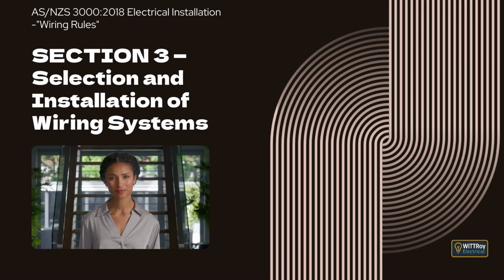The copper sheath must have enough cross-sectional area and conductivity so it can safely carry both neutral current and earth fault current. The ESR system is only permitted in installations that use the MEN earthing system, and it must start at the point where the neutral and earthing conductors are connected together to form the MEN connection. If at any point the combined protective earthing and neutral conductor is changed so that the neutral and the protective earth become separate conductors supplying electrical equipment, they must not be recombined later to form another PEN conductor. The ESR system must not be installed in hazardous areas. Conductors used in an ESR system must not be smaller than 2.5 square millimeters.